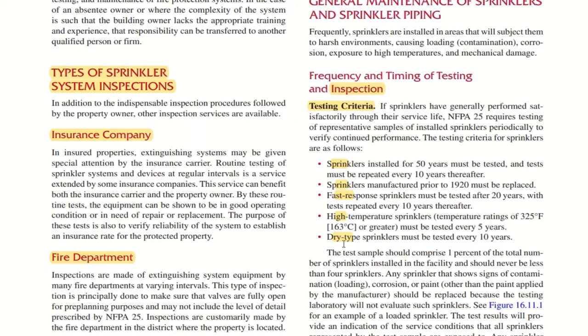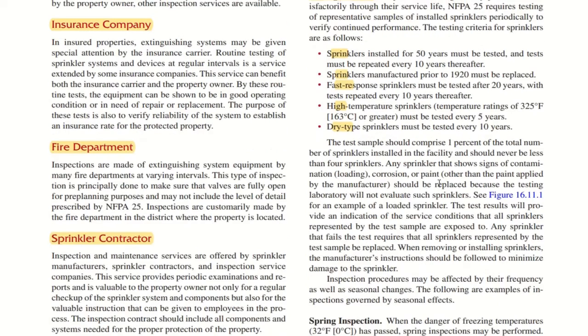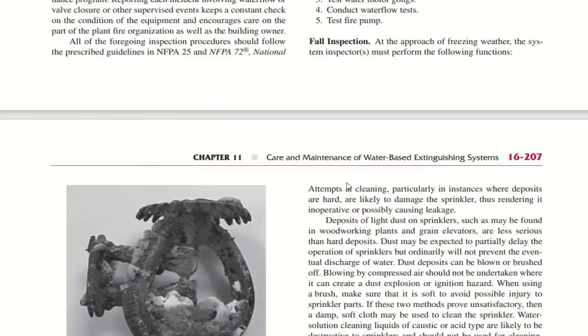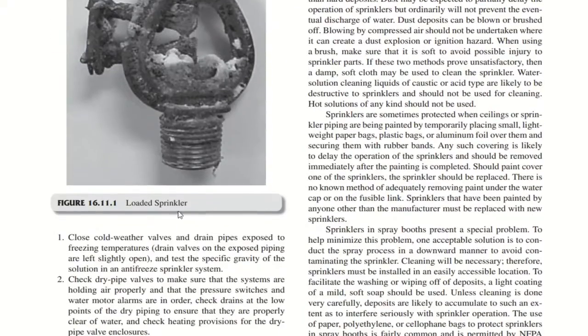Just go through. Dry type sprinklers must be tested every 10 years. High temperature sprinklers must be tested every 5 years. Fast response sprinklers must be tested after 20 years, with tests repeated every 10 years thereafter. Sprinklers manufactured prior to 1920 must be replaced. Sprinklers installed for 50 years must be tested, and the test must be repeated every 10 years thereafter. And these are all most important points. We have loaded sprinklers.